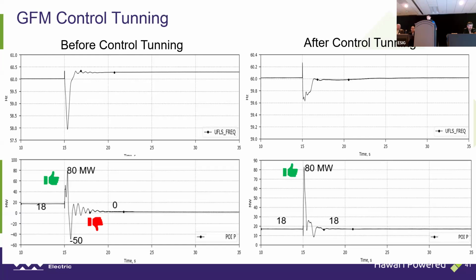So left-hand side is if we do not tune GFM, or if it is not tuned well, you can see during the fault the frequency dropped and the response of the resource jumped very high. But once the fault gets cleared, the response from the resource goes totally south. So we don't want to see, when the system tries to recover from a significant three-phase ground fault, this resource takes tons of power from the system. Yeah, this could make our frequency nadir really low and the frequency recovery really hard.